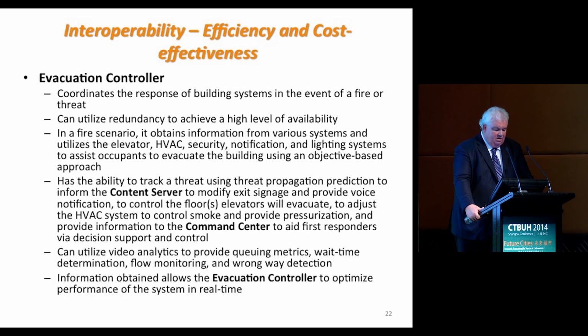It tracks the threat and using the information from the content server. So the content server then can modify exit signage and provide voice notification to control the floors the elevators will evacuate, to adjust the HVAC system, to control smoke and provide pressurization, and provide information to the command center to aid first responders.